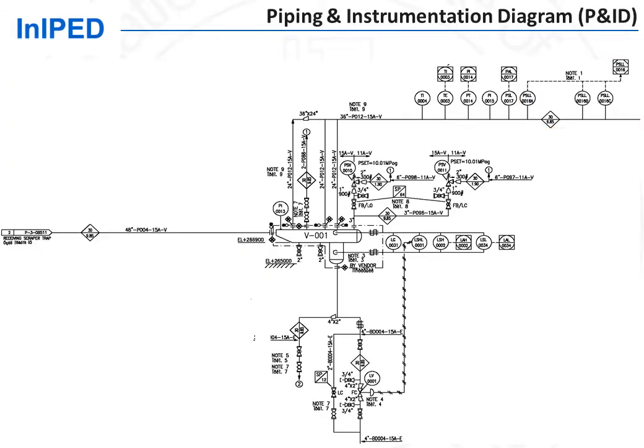As explained, P&IDs show all the features that are provided for operation, monitoring, process and emergency shutdown, as well as for maintenance. It is therefore an essential document fully depicting the future operating facility. It is subject to a comprehensive review between the engineer and the plant owner. P&IDs must indeed comply with the operator's operation, process automation, safety requirements, as well as maintenance practices. The P&IDs are therefore subject to revision. Their initial issue is called issue for review and is reviewed during a meeting between the engineer and the plant owner, the future operator.